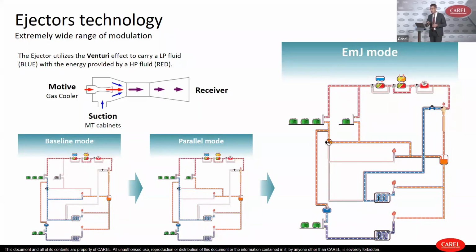in order to be pumped into the receiver. So if we look at the EMJ mode on the right of the slide, you can see that with the CAREL configuration, all the fluid that is coming from the medium temperature cabinet is managed by the ejector and pumped into the receiver. At the same time, by switching the three-way valve, the medium temperature line and the parallel compression lines are working at the same level of pressure and are bringing the fluid from the receiver. So we have two main benefits. One is that most of the mass flow is managed by the ejector, so all the medium temperature load is managed by the ejector and doesn't need to be managed by the compressors. And the other benefit is that all the lines are taking the gas from the receiver at a high level of pressure, reducing the delta P and the workload conditions for the compressors.